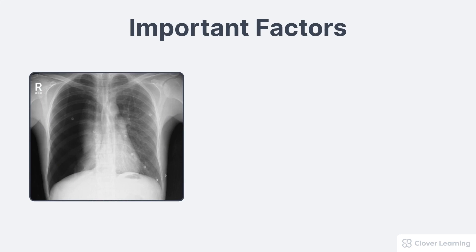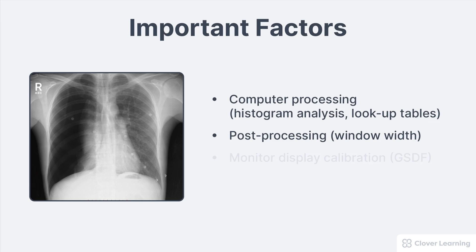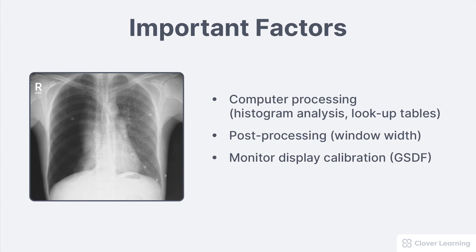The most important factors controlling image contrast are computer processing like histogram analysis and lookup tables, post processing like adjusting the window width, and monitor display calibration called the grayscale standard display function or GSDF. If any of these factors are wrong, the image contrast can be significantly degraded.